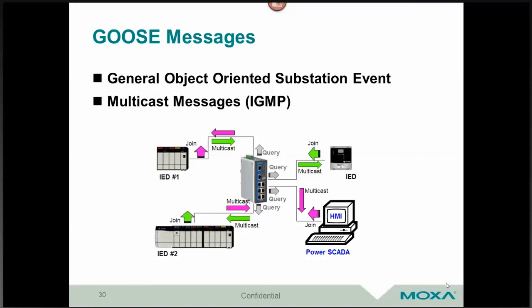Without IGMP, what will happen is that an IED might send some information, and it'll have to be broadcast to everybody. The problem is that not everybody wants to hear it, and that becomes very inefficient bandwidth-wise on your network. So you really want to keep that bandwidth under control so messages get through in a timely manner. IGMP is a way to do that, and that's how GOOSE messages are used today.